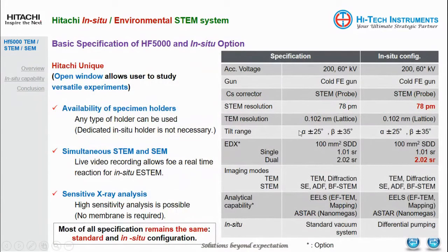And yep. The whole point is to highlight that even with the in situ experiment, it won't affect the basic specification of this HF5000. Like the STEM lattice resolution is 78 picometer. When you do in situ with gas induced, you still can achieve 78 picometer for the atomic resolution imaging. All remain the same because of the lab in-gap design.